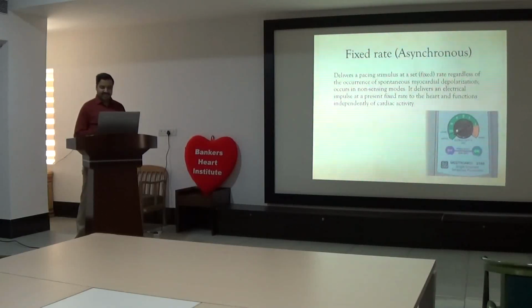So the first type of pacing with this is fixed rate or asynchronous pacing. For this mode, you have to set this knob to the asynchronous position, and it delivers a pacing stimulus at a set fixed rate, regardless of the occurrence of spontaneous myocardial depolarization. And it occurs in non-sensing mode, because asynchronous means sensitivity is out. It delivers an electrical impulse at a preset fixed rate to the heart and functions independently of the cardiac activity. Many times we may require this.